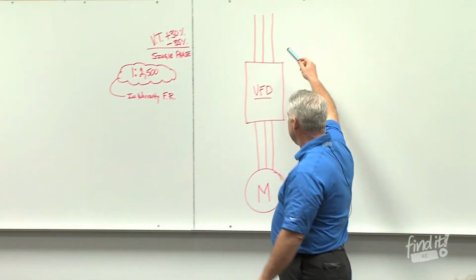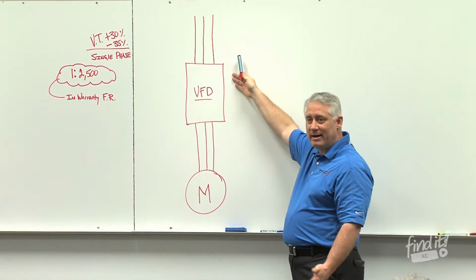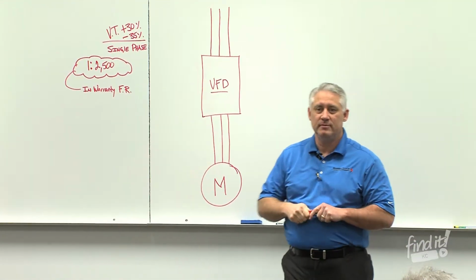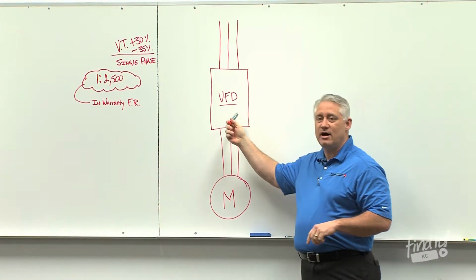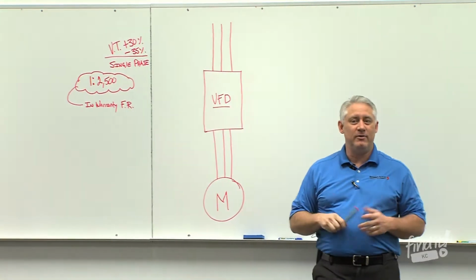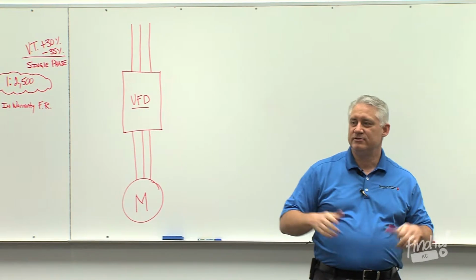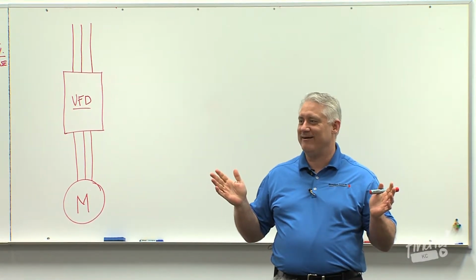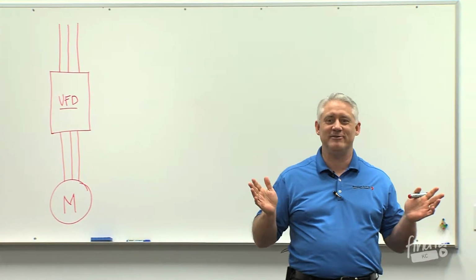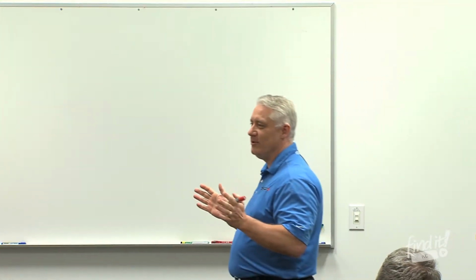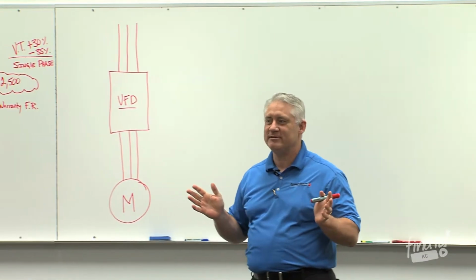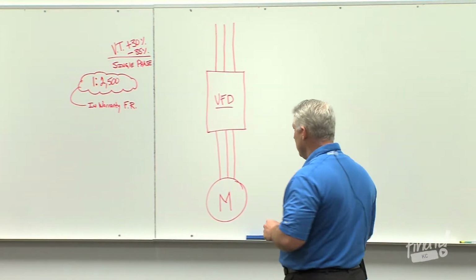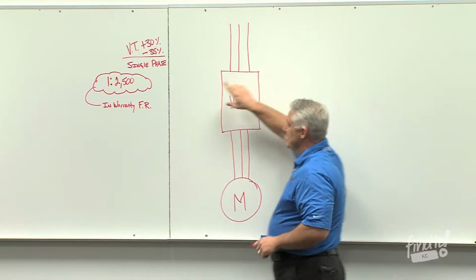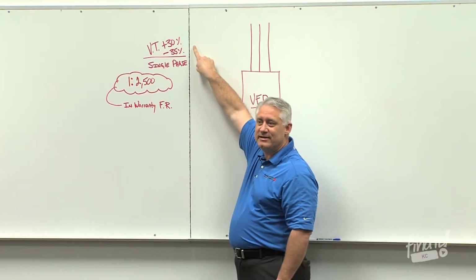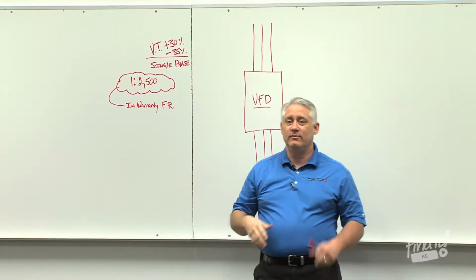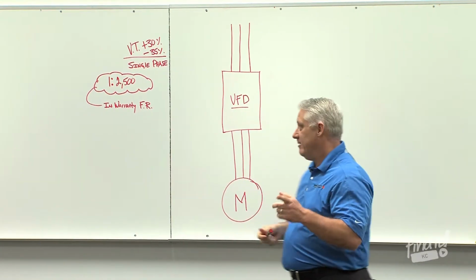This is a three-phase drawing of just a VFD with no bypass on the wall in your mechanical room. Anybody have an idea of what the voltage tolerance is that a drive on the wall without a bypass has today? So you all have perfect power in your buildings, right? No brownouts? No single phase scenarios where you get a single phase for a short period of time? Nobody's burning up contactors, no contactor failures. We've all seen them, we all have them. So what a VFD on the wall can do is it has a voltage tolerance of plus 30, minus 35%. So that's a big voltage tolerance. So keep that in mind as we move forward.